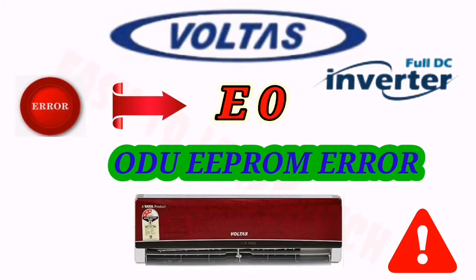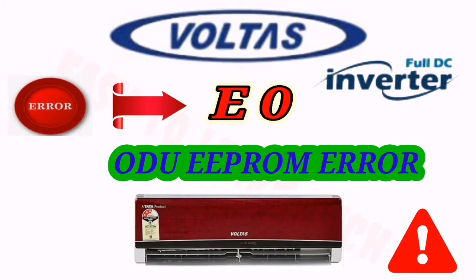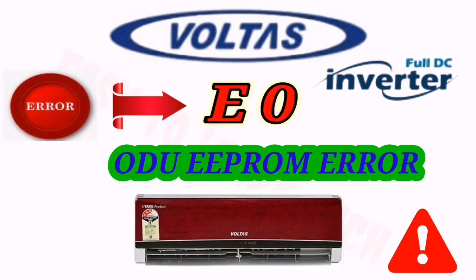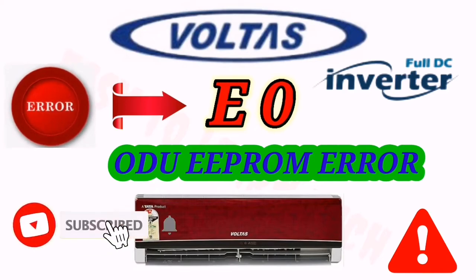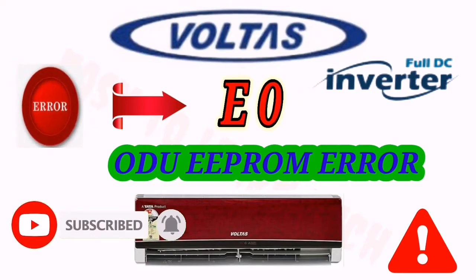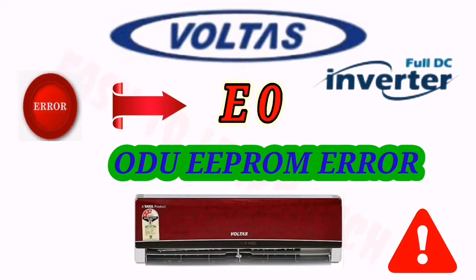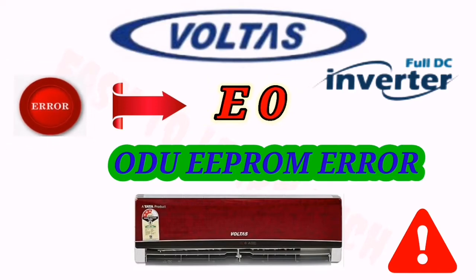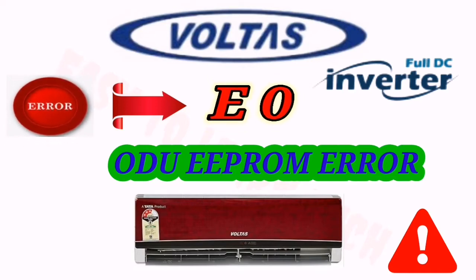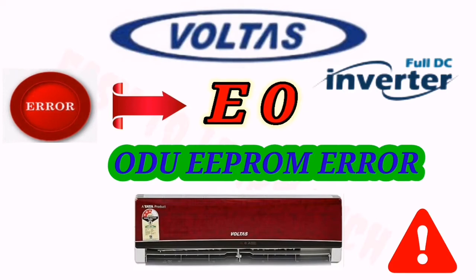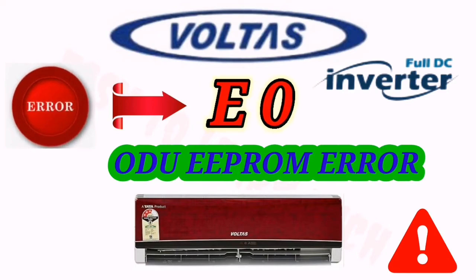You can do only one thing: reset your air conditioning. Put the power off, wait for 3 minutes, and restart the unit. And again, if you get the same error E0, it means the EEPROM in your outdoor PCB is faulty. You need to change the outdoor PCB. When you change the outdoor PCB, your unit will be in working condition.